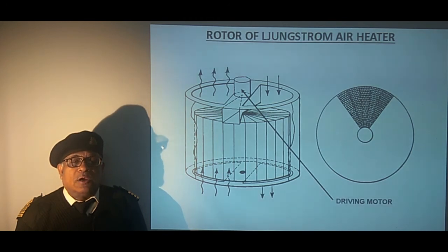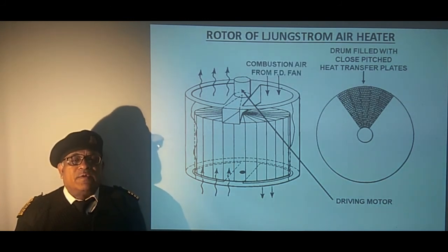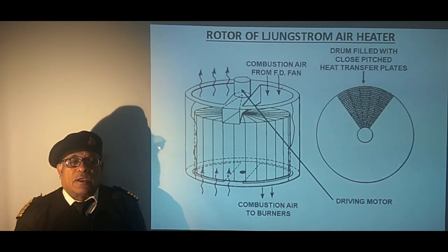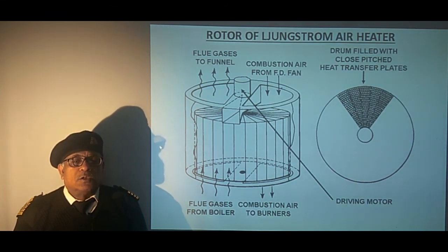First of all we have the driving motor rotating this rotor through reduction gearing at a very low rpm. Then it is shown that very close pitched plates are fitted in this rotor which are in segments. The combustion air from FD fan comes from the right side of the rotor passage and it goes to the burner. On the other hand the flue gas which is entering from the bottom on the left side it passes up to the funnel. So when the rotor gets heated through the passing in the flue gas passage it gives its heat to the air and thus the air gets heated and goes to the burner.